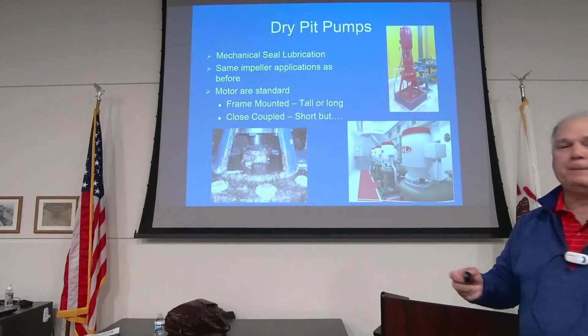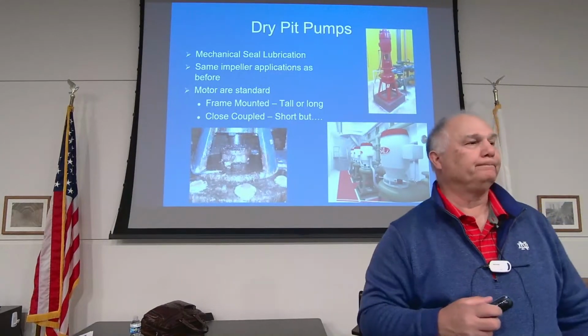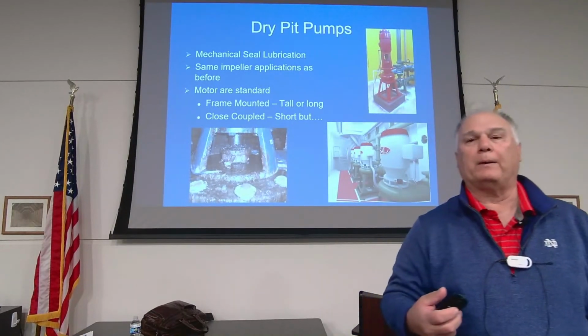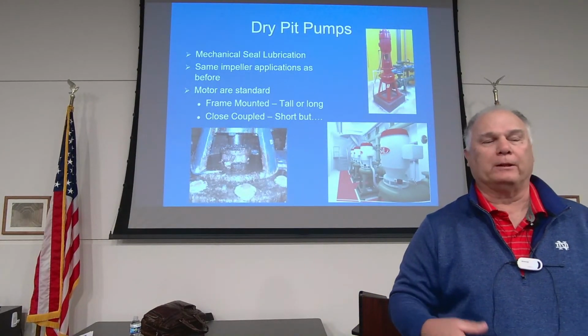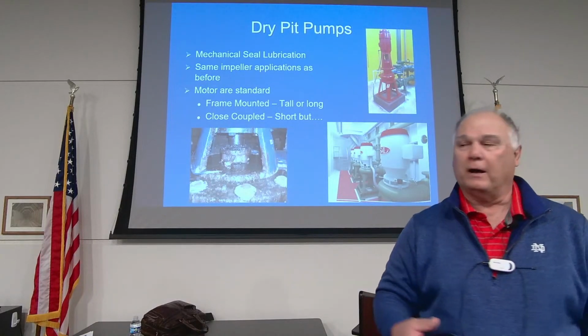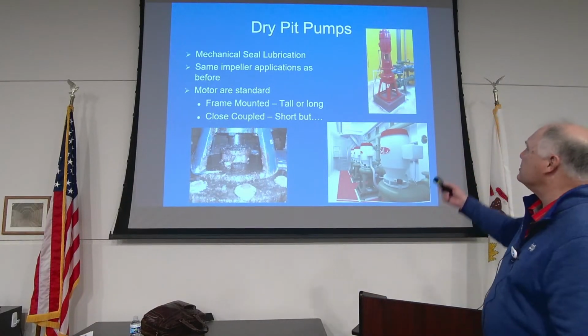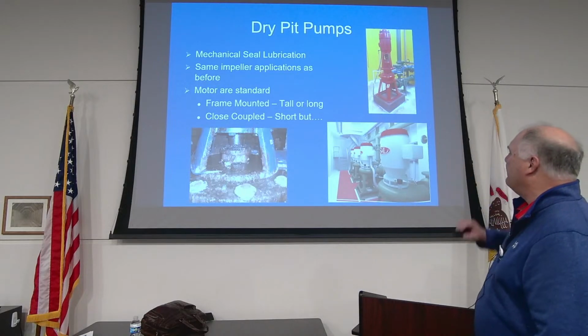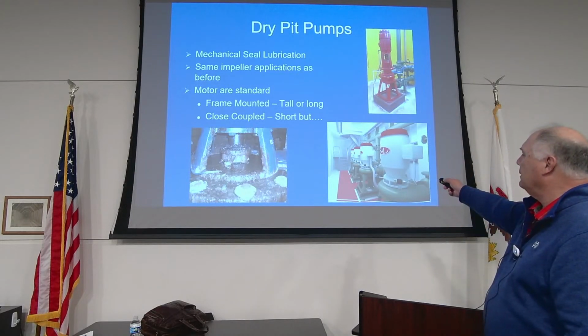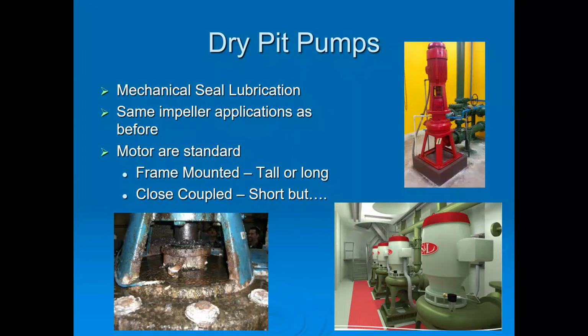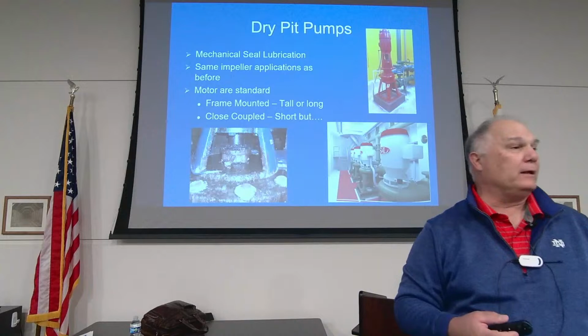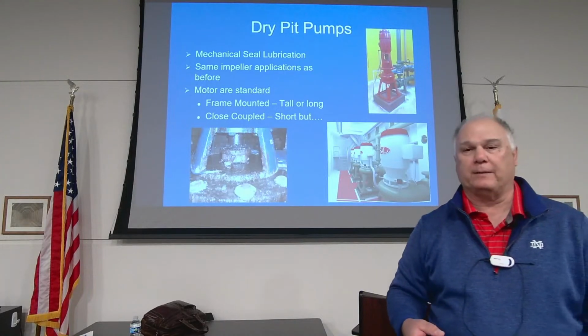So how many people have dry well, wet well pumps? For people that have dry well, wet well pumps, we talk about mechanical seals, we talk about lubrication of that seal. These are single mechanical seals. This is a frame-mounted pump, single seal, close coupled pump, and we put water in that seal to keep it cool, whether it's a mechanical seal, whether it's packing, whatever the case happens to be.